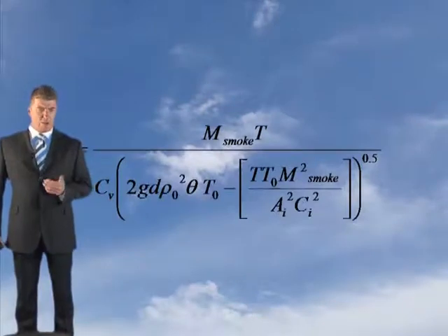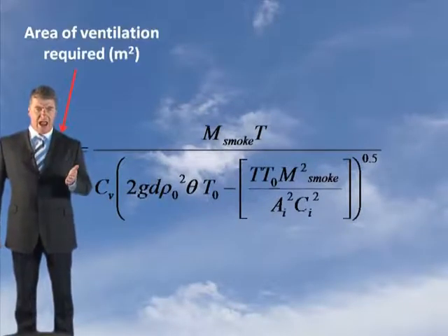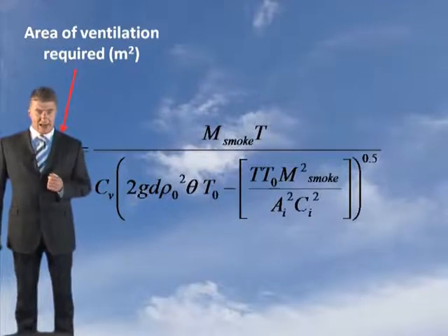Now there's another option from PD 7974, and that's as follows, as you can see here. This is expressed as an AV, not an AV-CV factor. It's taken account of the coefficient in the formula itself, so it comes out as an AV factor. This is a formula here, where your AV is the area of your ventilator. This is a geometric area.